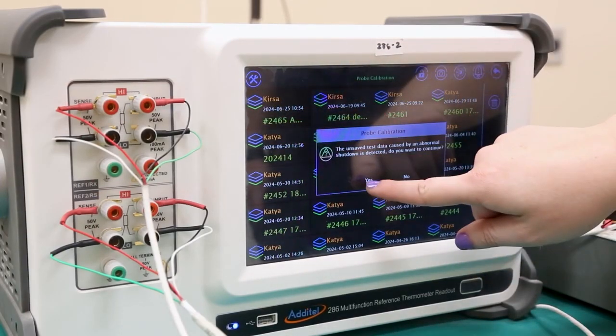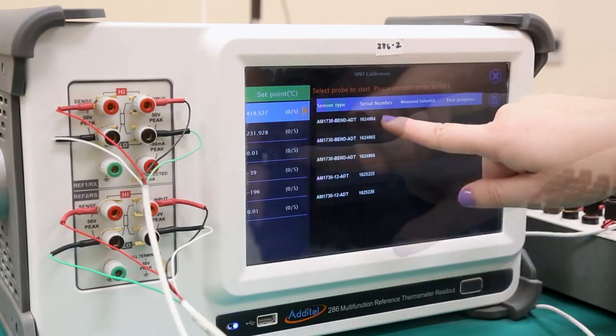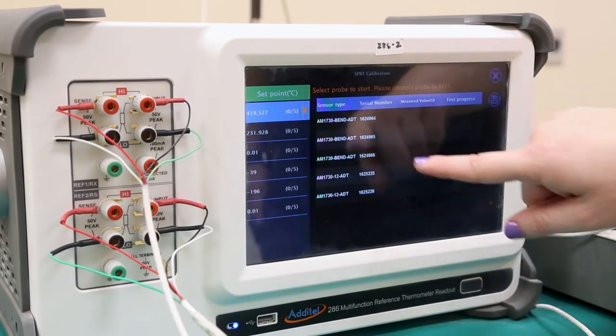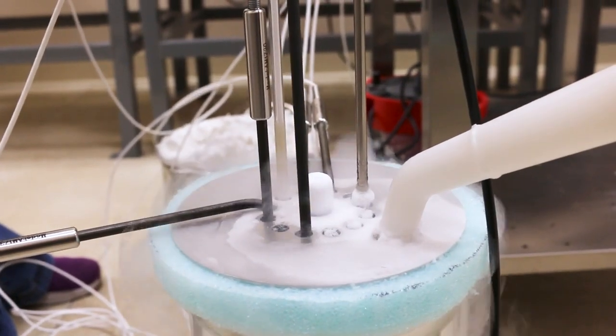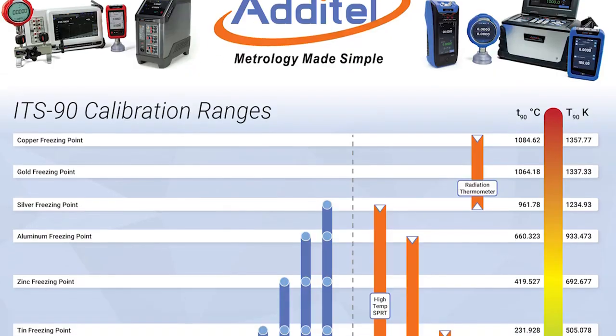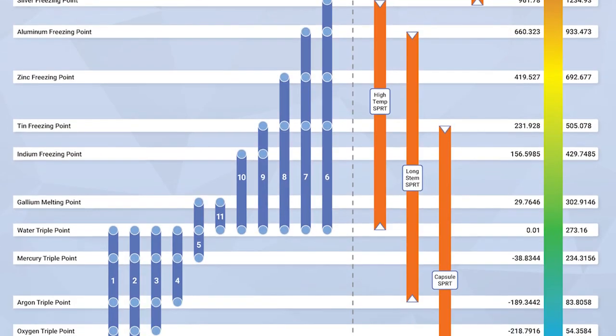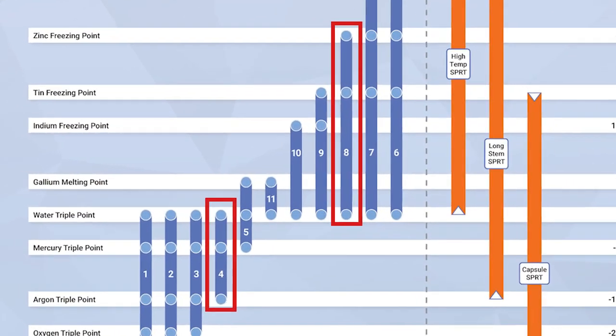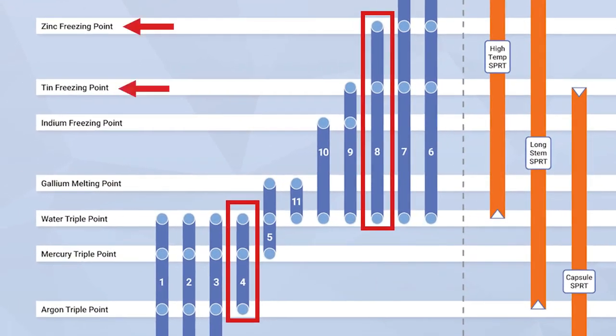This video will take a look at how the Additel 286 can be used as both a temperature bridge and measurement device to perform a repeatable fixed-point calibration of 5 different temperature probes with as little user input as possible. The ITS-90 subranges used in this demonstration will be 4 and 8, covering the freezing points of zinc and tin, the triple point of water, the triple point of mercury via comparison calibration in a liquid bath, and the triple point of argon via comparison calibration using a liquid nitrogen comparator.